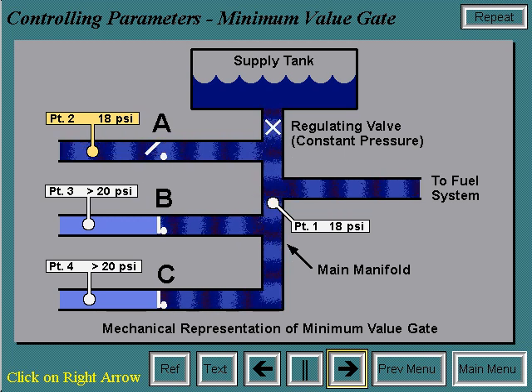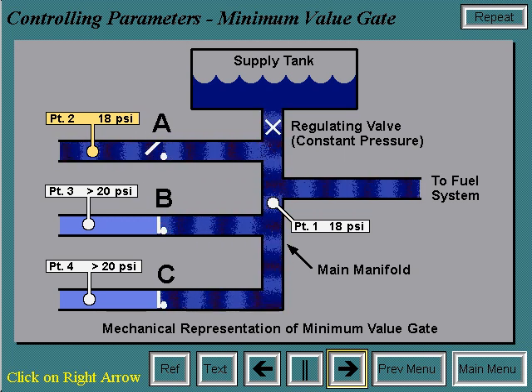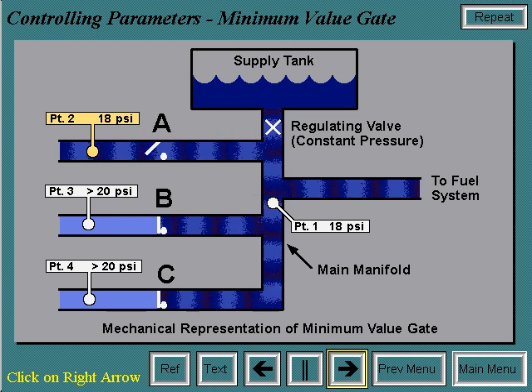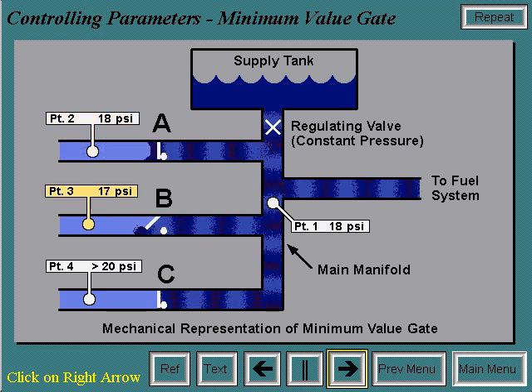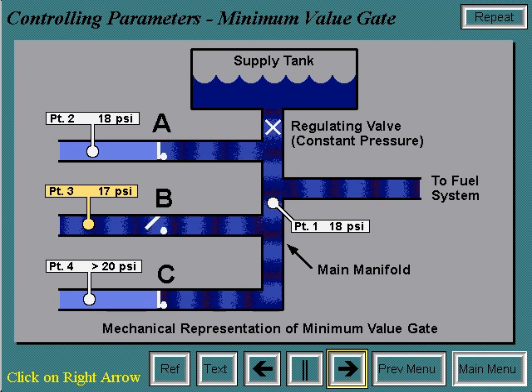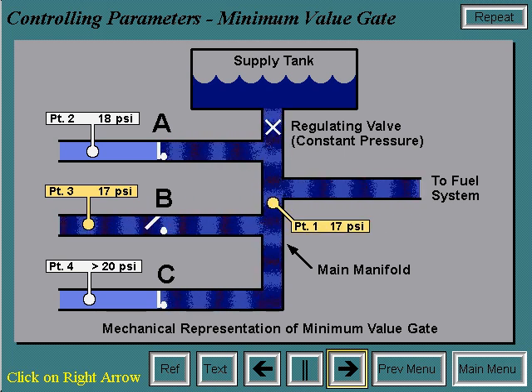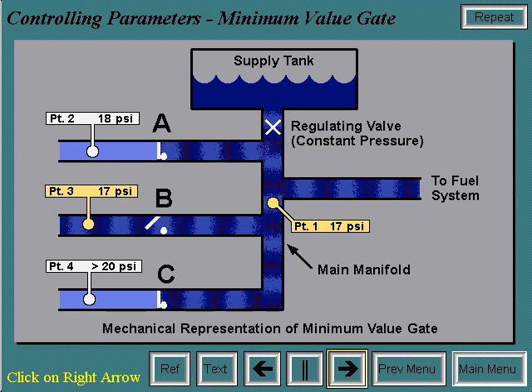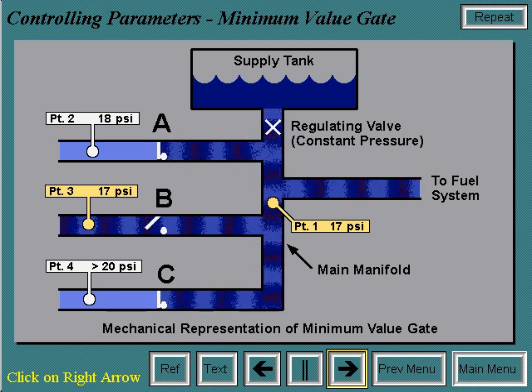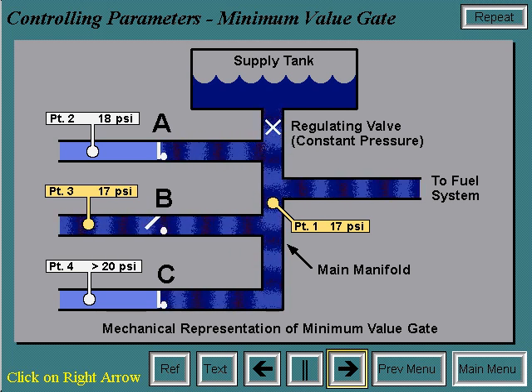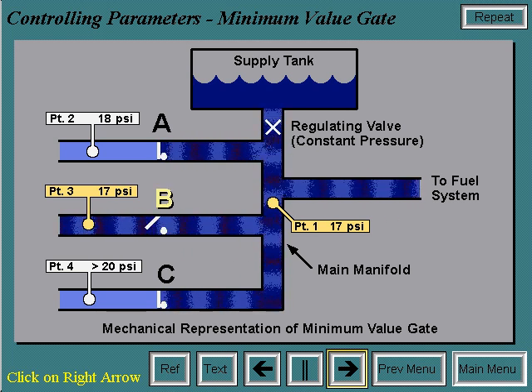As the operating conditions change, the pressure requirements at points 3 and 4 change. As the pressure at point 3 drops below 18 psi — for example, 17 psi — the manifold pressure will be brought down to 17 psi, causing check valves A and C to close and check valve B to open. Therefore, system B is now controlling.